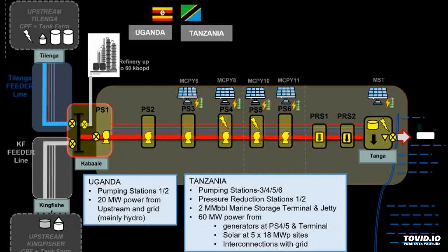But if flow rates and pressure come down, it will cool more as it moves, threatening to solidify and block the flow. To get round this, two heating stations have been added to the design, capable of boosting the crude oil temperature back towards 80 degrees Celsius to ensure strong flow. Heating cables will run down the entire length of the pipe using a technology known as long line heat tracing (LLHT), which works on a similar principle as a kettle element, using resistance to generate heat when an electric current passes through a specially chosen high-resistance filament.